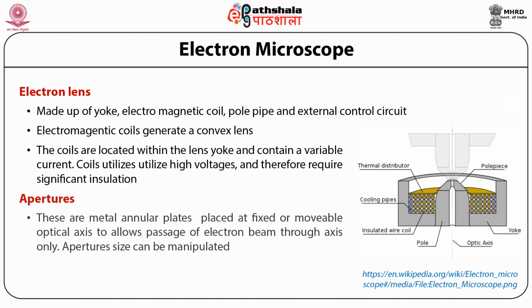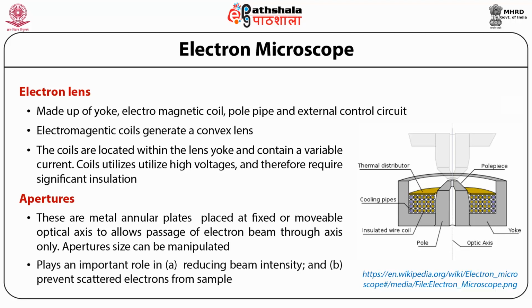Aperture. These are metal annular plates placed in the fixed or movable optics so that they allow the passage of the beam through one axis only, and this aperture size can be manipulated. That's why we can manipulate the intensity of the electron beam that is passing through the sample. It is also very important so that any scattered beam resulting from the sample is prevented from going back to the objective lens and getting imaged.